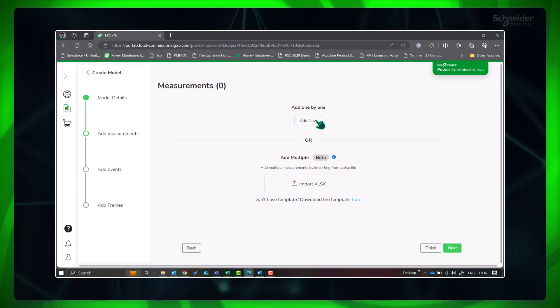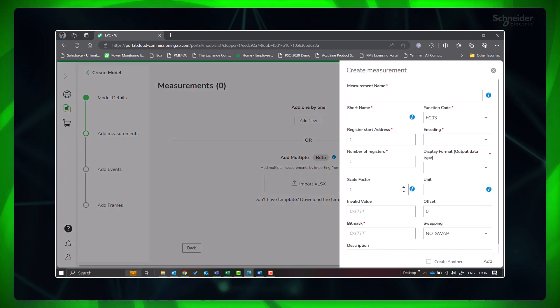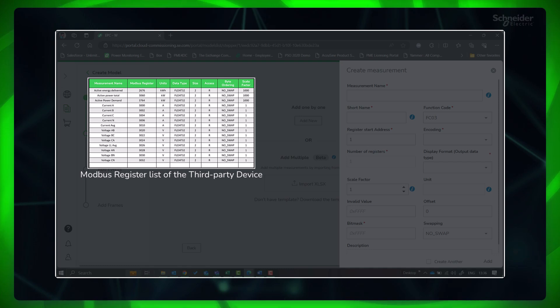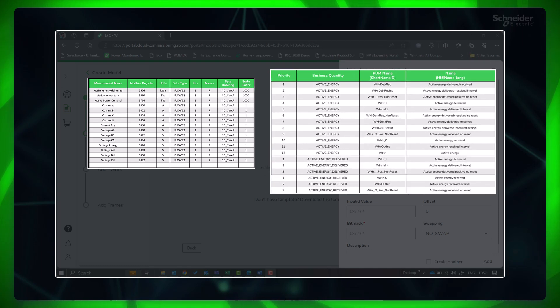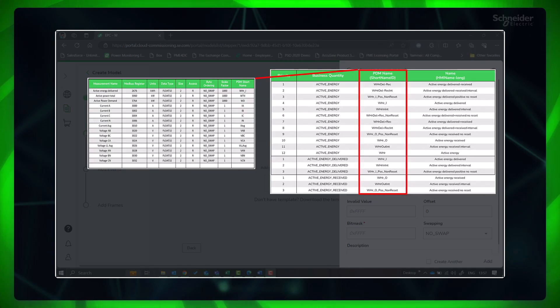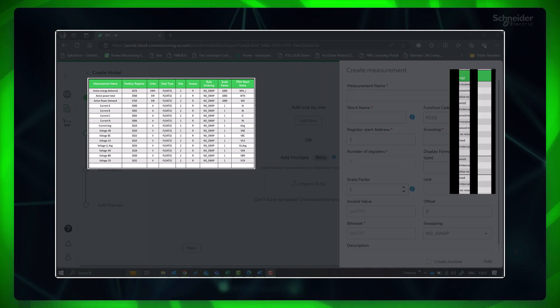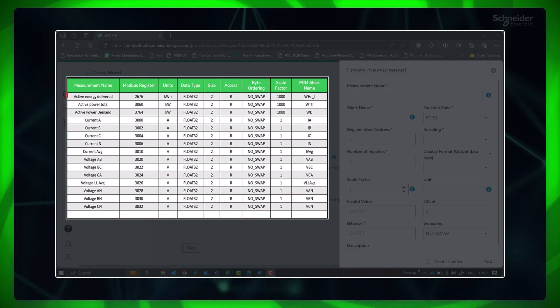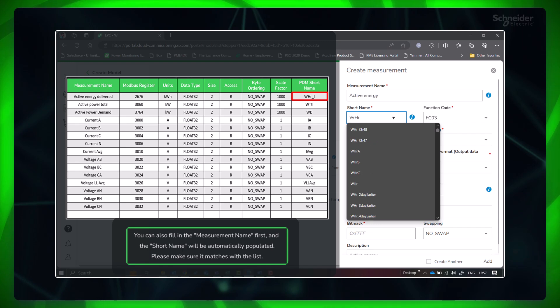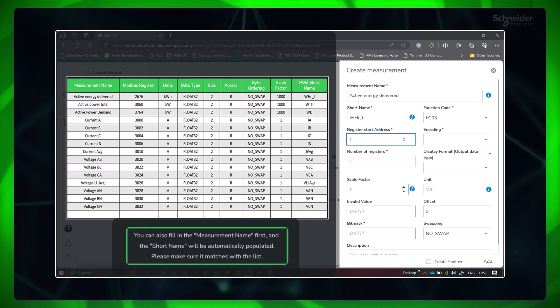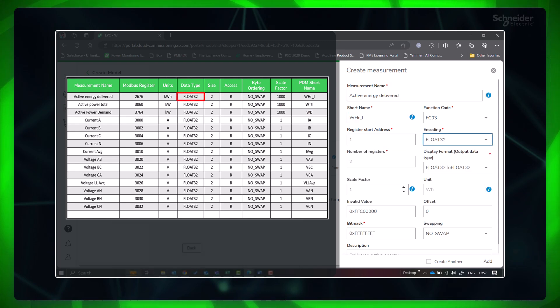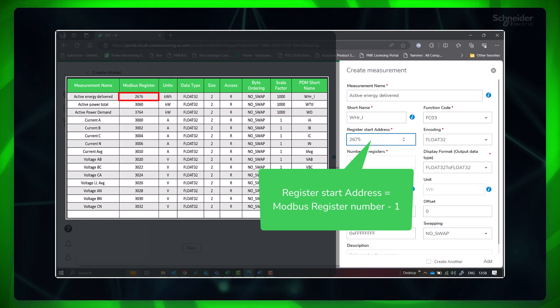We can add measurements one by one or import them in bulk using a template. Let's do it one by one. Click 'Add New.' From the Modbus register list of the device and Appendix C in the downloaded document, select the business quantity, measurement name, and the respective PDM short name. Update the respective short name against each measurement in the register list to refer to later. The first measurement is active energy delivered. Select the short name taken from Appendix C and provide it in the field; the measurement name will be automatically populated.